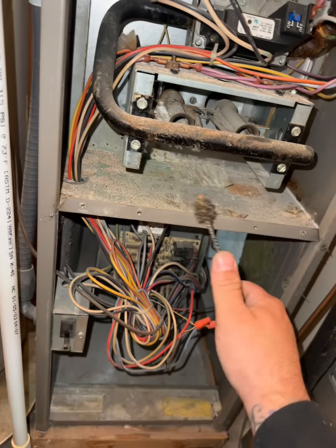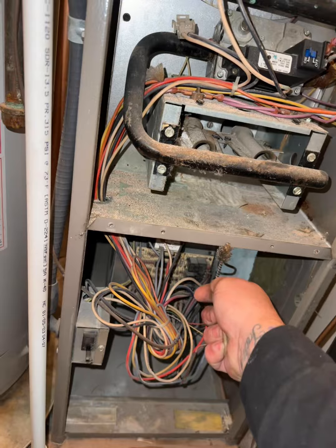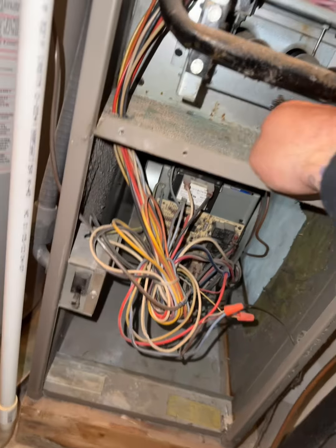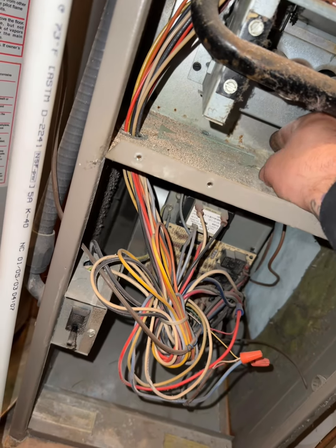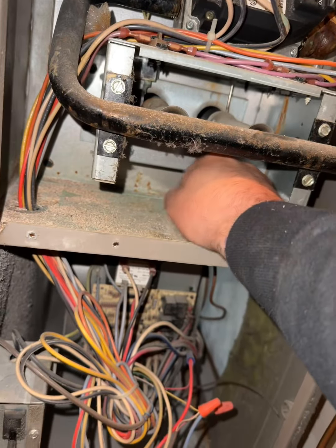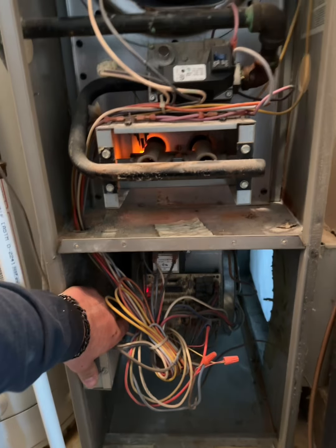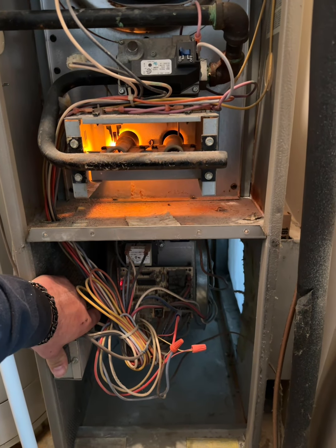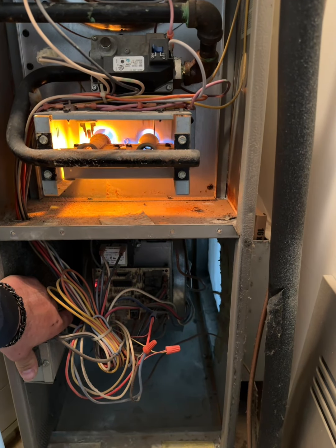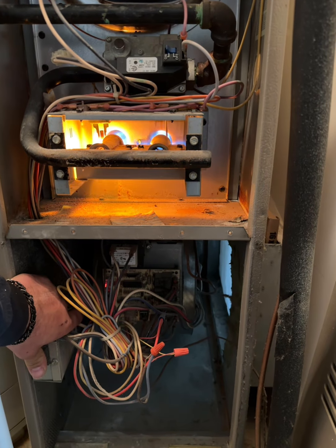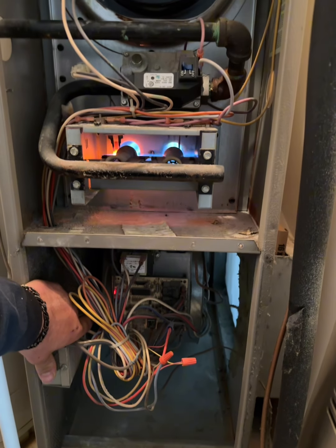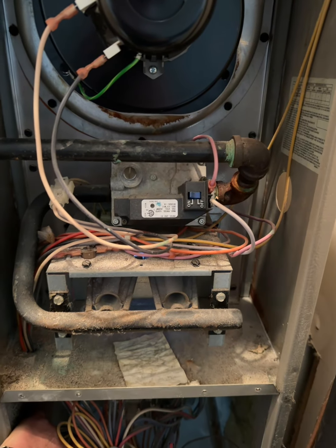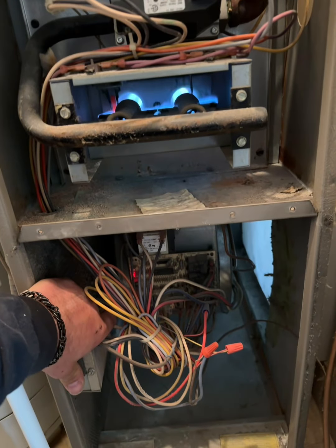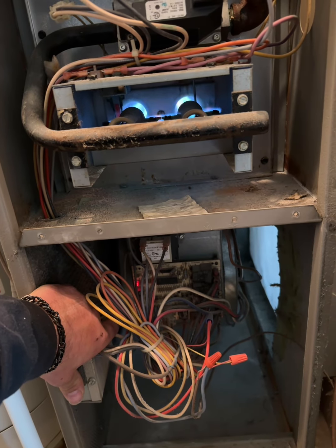So we're just gonna clean this up. What we'll do is bend this so we can clean that. And it's just a simple little movement. As you can see, we are cleaning the flame sensor. All right, so we got a clean flame sensor here. Igniter is about to come on. It is on. Let's see if that flame sensor was the problem. So flames would have gone out already. Let's see if we can get the blower motor to come on. This is an apartment building. For a customer, definitely take that gas valve out and correctly clean this. But here we are. That's call one done. Flame sensor.